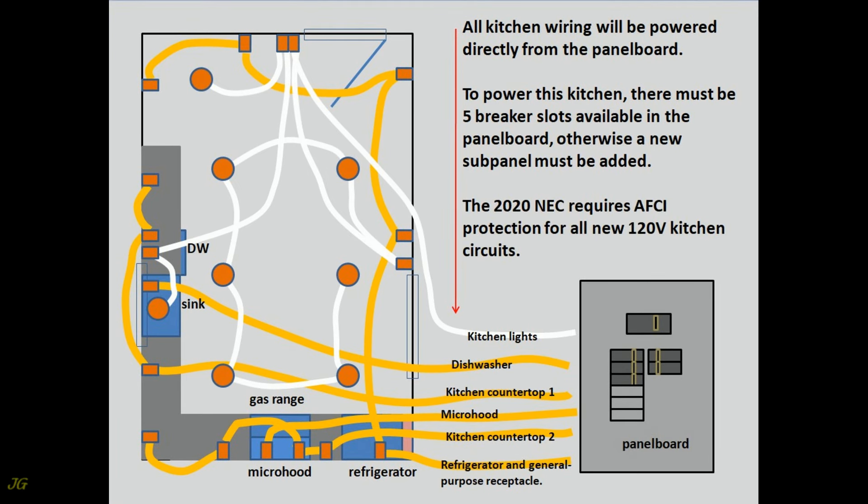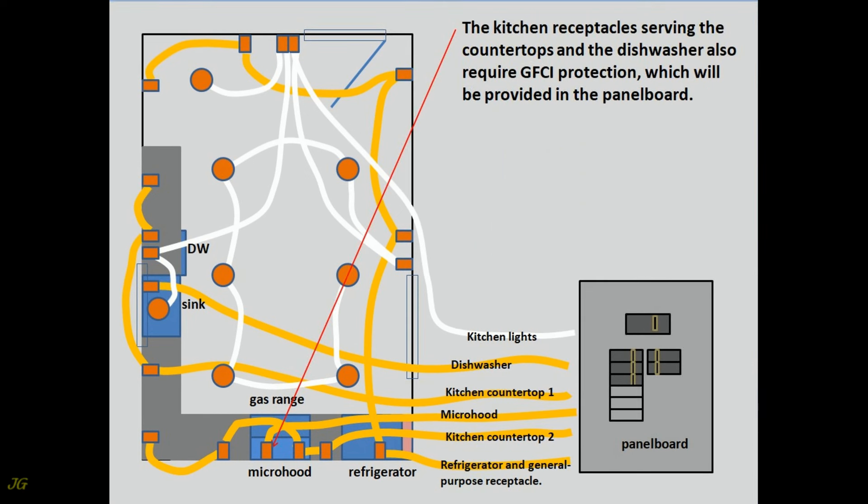The 2020 NEC requires AFCI protection for all new 120 volt kitchen circuits. The kitchen receptacles serving the countertops and the dishwasher also require GFCI protection, which will be provided in the panel board.